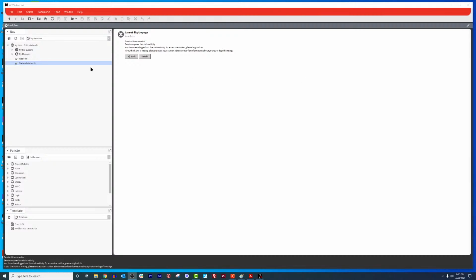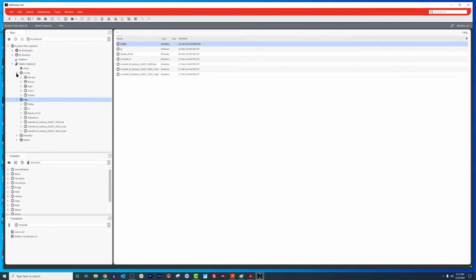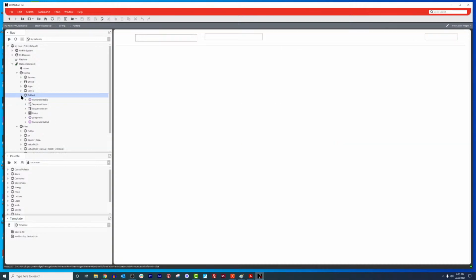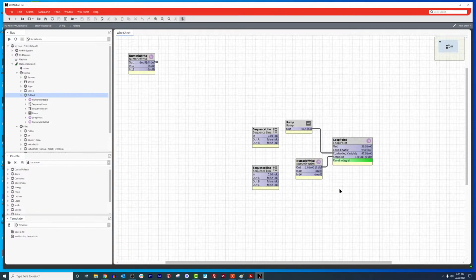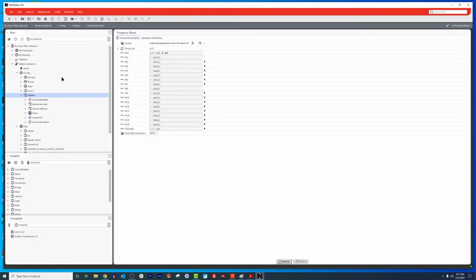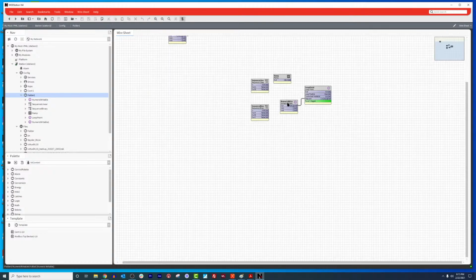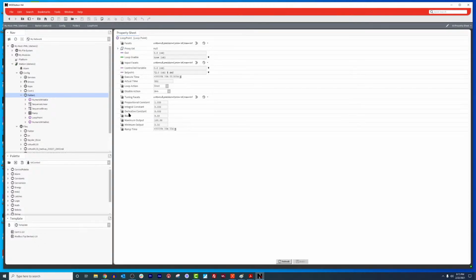All right, let's log into the station. Let's take a look. I should have one in folder 1. Let's go to Wiresheet View. Okay, let me disconnect this ramp real quick, and let me set my set point to 72. Zoom in a little bit because I know this can get a little small. Let me take a look at what my settings are in here.